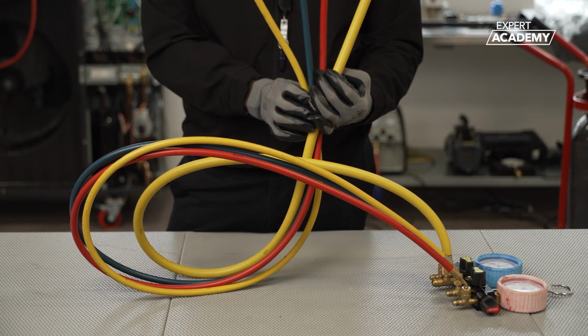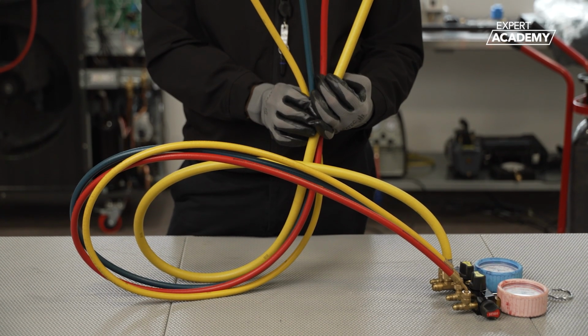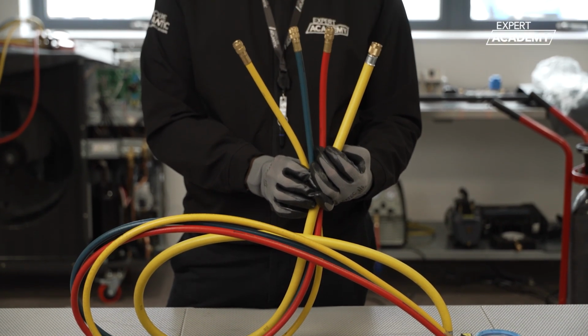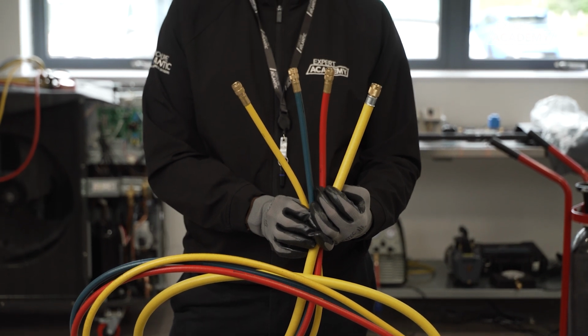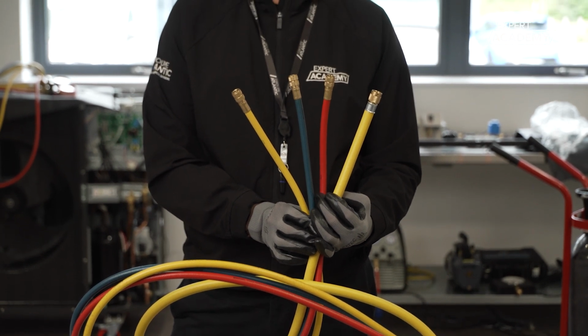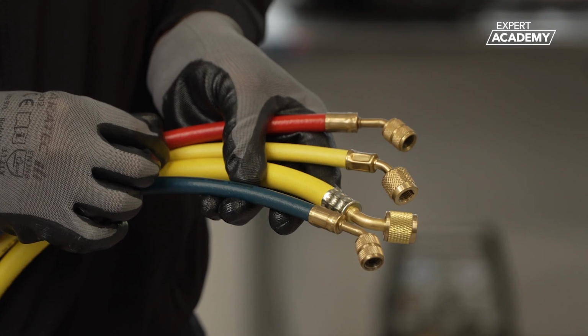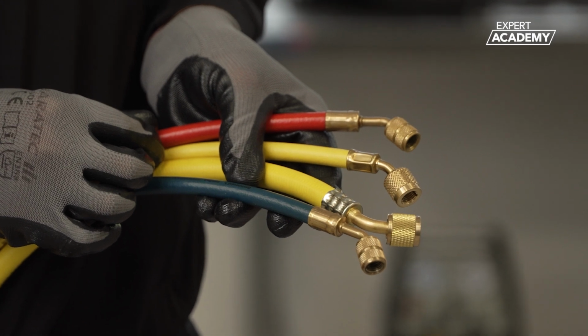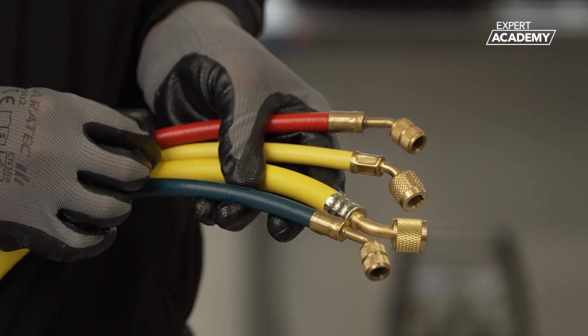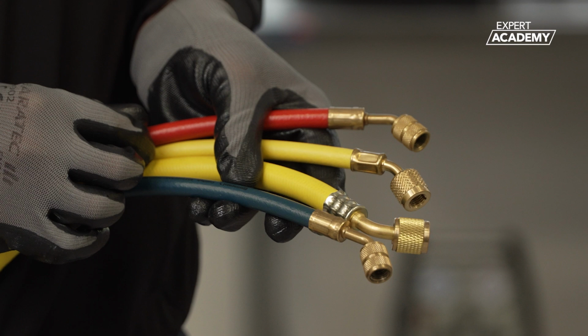To connect your various pieces of equipment to the heat pump system, suitable hoses are needed that are rated for the correct pressure and type of refrigerant you are working with. To attach the hoses, a variety of fittings are available, including some that make the job much easier with angled stems and quick release.